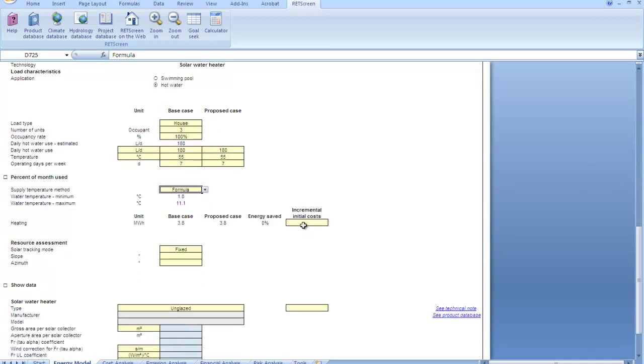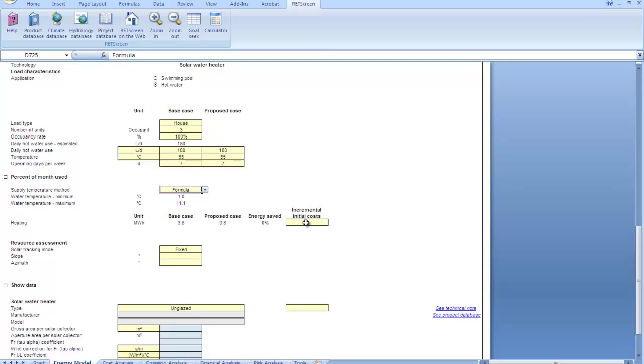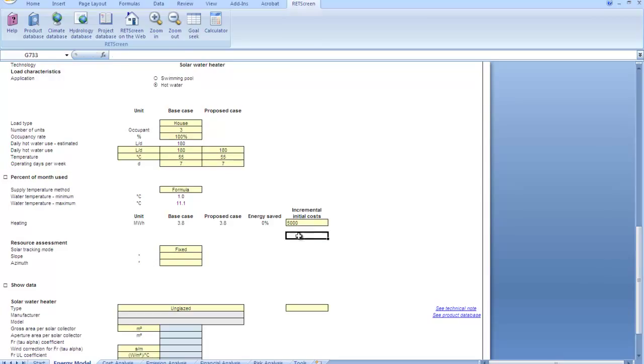And now RETScreen is suggesting 180 liters per day as typical use for three people. Because that's in white, it's just a suggestion. If you want to actually use it in the analysis, you need to enter it yourself down here in the yellow boxes. We're going to make base case and proposed case the same, and 55 will be my delivery temperature, and we operate seven days per week.